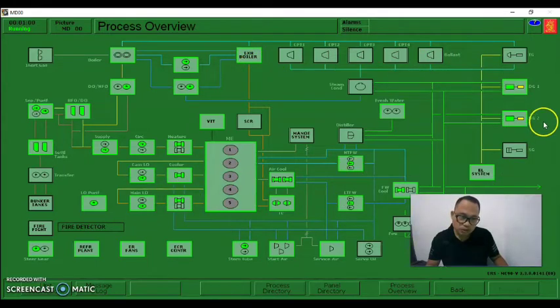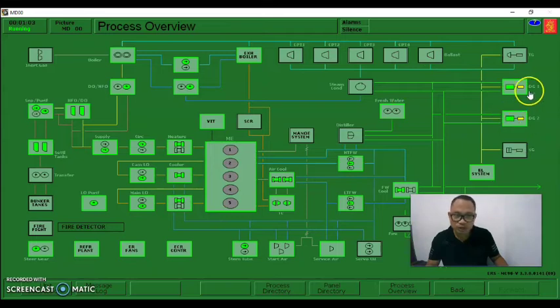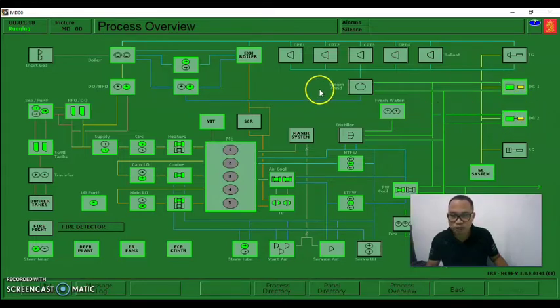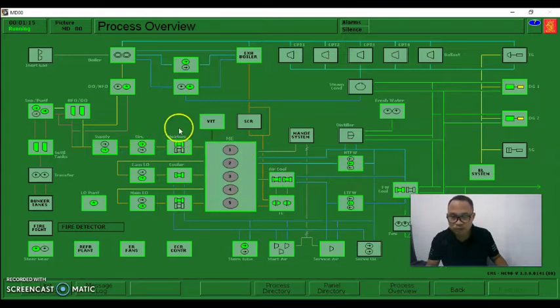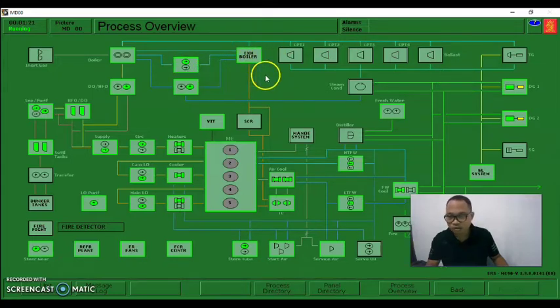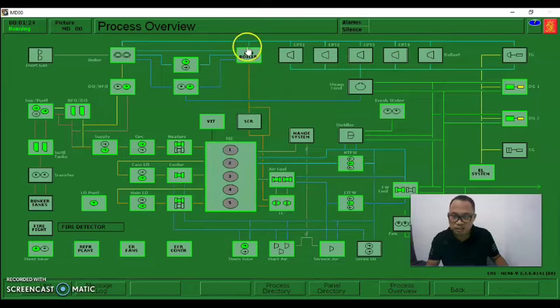So the generators - we have two diesel generators running: DG1 and DG2 in this process overview. DG1 is running and DG2 is also running, and our main engine is also running with no alarms. Same with the diesel generator - no alarm. Auxiliary boiler is in operation and there is no alarm.